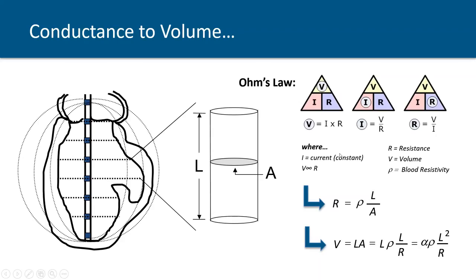Now, if we blow up one of these segments, we indicated that they're modeled as cylindrical discs, basically just stacked up inside the left ventricle. The resistance for each of these cylinders is provided by electrical theory of a conductor, and it's related to the resistivity of the material inside that cylindrical disc. It could be blood, could be saline, multiplied by the distance between those electrodes and divided by the cross-sectional area of that segment.